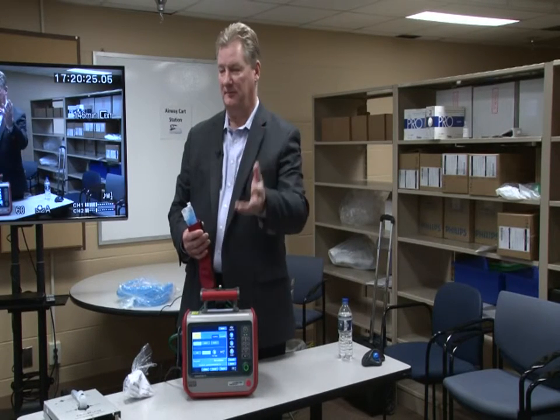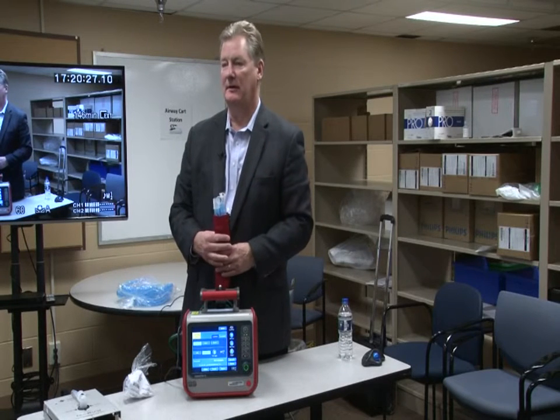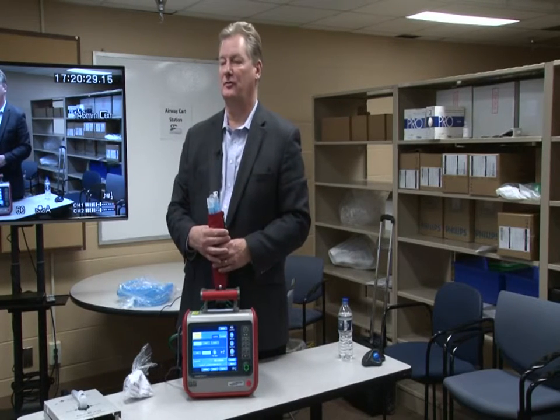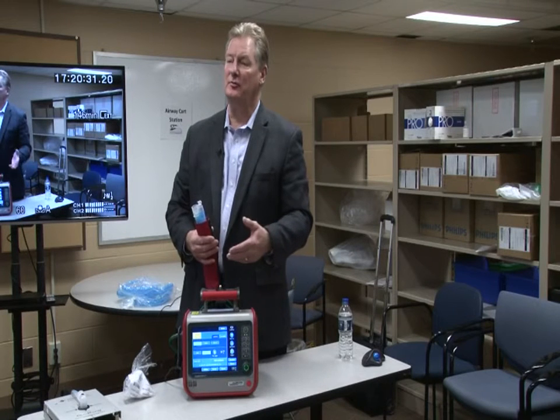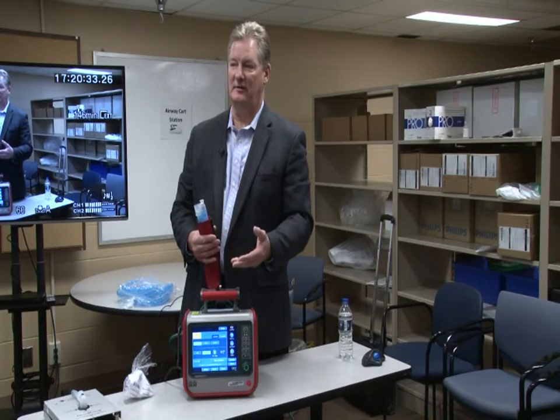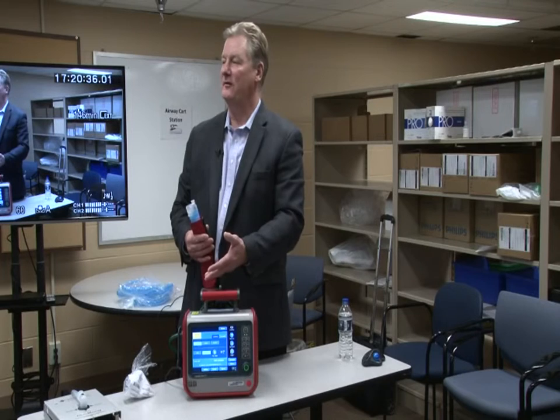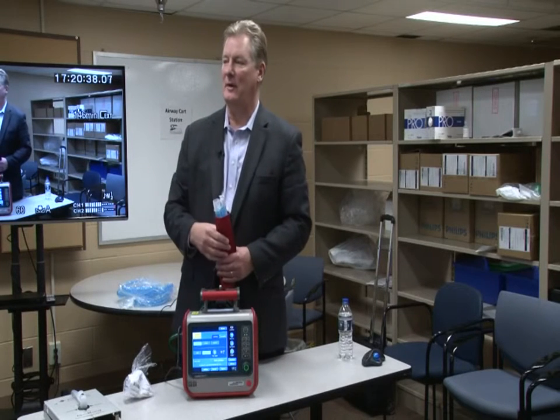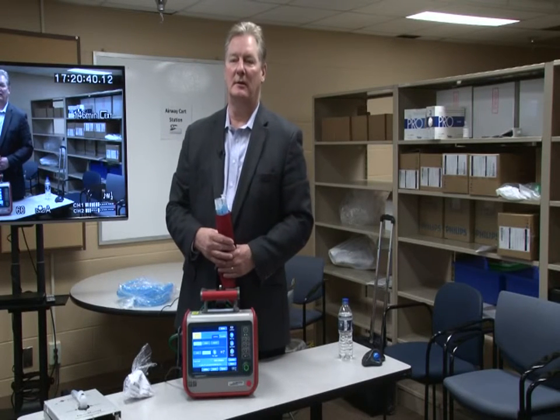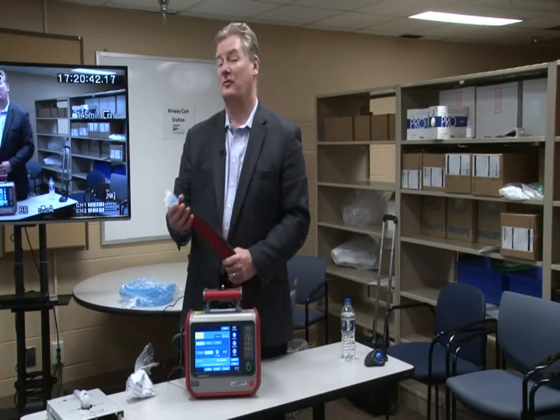And of course, unless you had some nastiness in the tank, but that's going to go through some internal filters as well. And then the expiratory gas and any fluid that gets into the circuit doesn't go into the ventilator anyway, because it stays on the outside of that white membrane. So, how often does that white membrane need to be replaced? When it doesn't work. Okay.